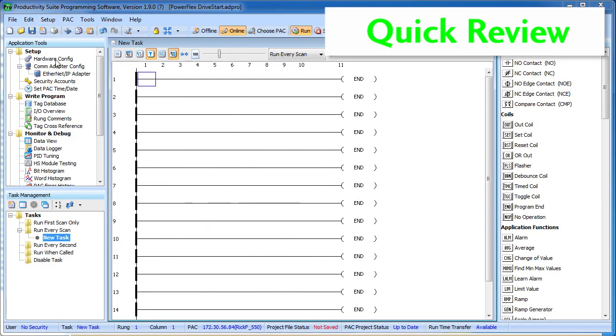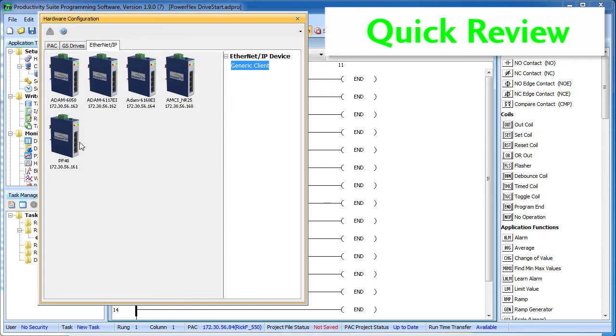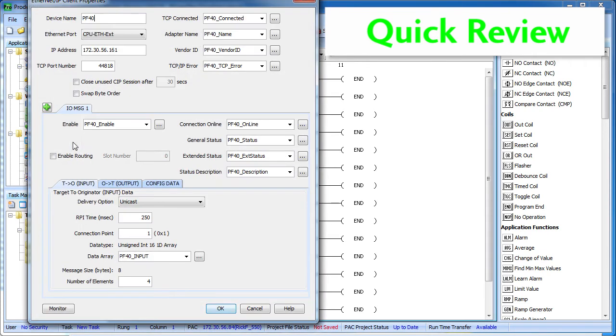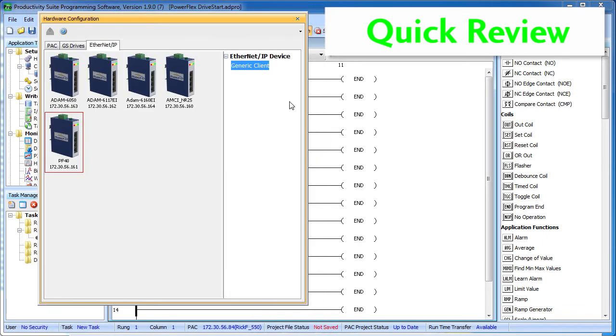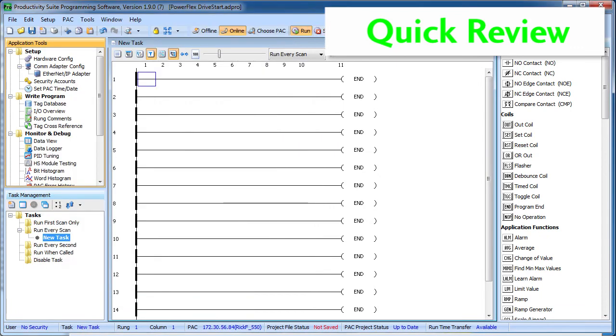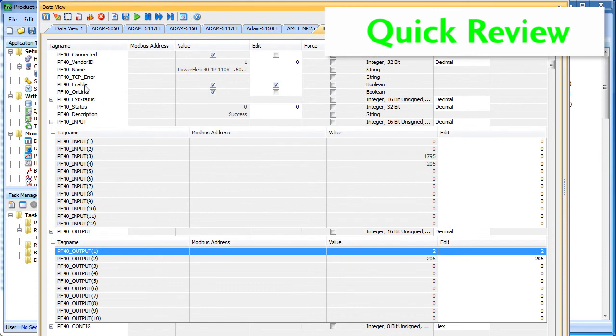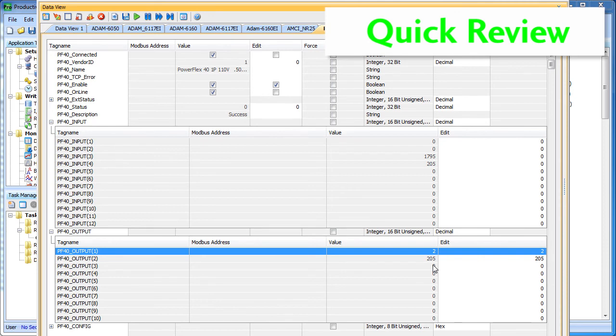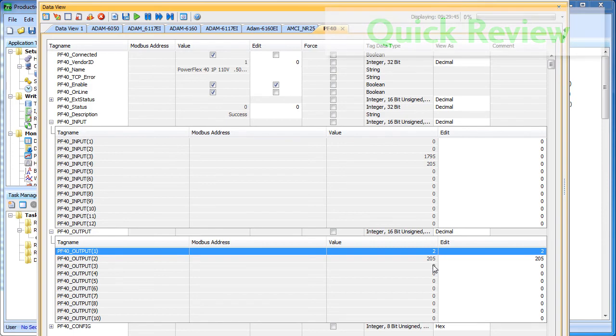All we did was drop a generic client onto the screen here in the hardware configuration and fill in the blanks. We also hit that monitor button to automatically create that data view for us. Once that was done, we transferred the program down to the controller and opened up our data view. From the data view we enabled the messaging, again your ladder code would normally do that, we verified we had a good connection and then we could tell the drive what to do and what frequency to do it at right here in this output array. When we entered these values, the Ethernet IP protocol automatically took those and transferred them down to the drive. Easy.